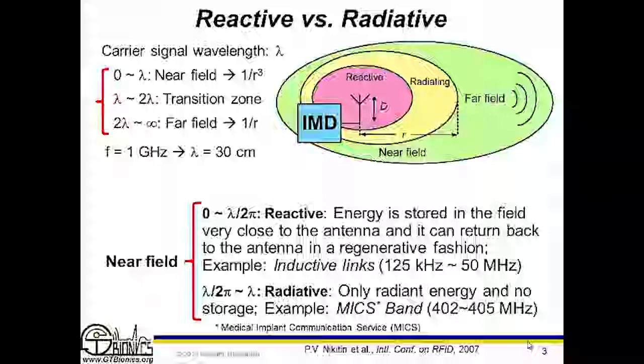and the rule of thumb says that as you deliver the power from outside of the body into the body, the temperature at the surface of your implantable device shouldn't increase by more than 1 degree centigrade. So when that's the constraint, that's the limit, because if you do, it's as if the tissue around this implanted device is experiencing fever. So you can handle 1 degree, 1.5 degree fever for a while, but if you go with a 2 degrees centigrade fever for a long time, you start causing damage.